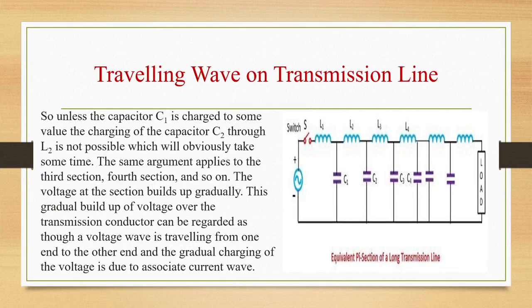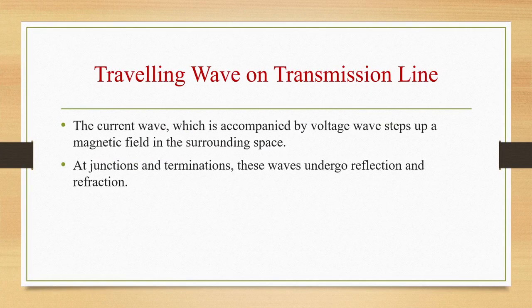This diagram shows the equivalent pi section of a transmission line. Unless capacitor C1 is charged to some value, charging of capacitor C2 through L2 is not possible, which takes some time. The same argument applies to the third, fourth sections and so on. Voltage at each section will build up gradually, and this gradual buildup can be regarded as a voltage wave traveling from one end to another. The gradual charging is due to the associated current wave, which sets up a magnetic field in the surrounding space. At junctions and terminations these waves undergo reflection and refraction, and total energy of the resultant wave cannot exceed the energy of the incident wave.